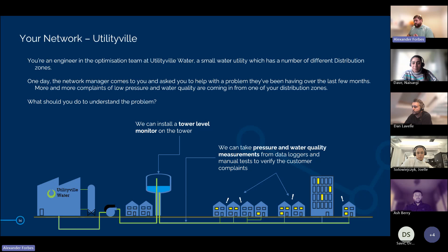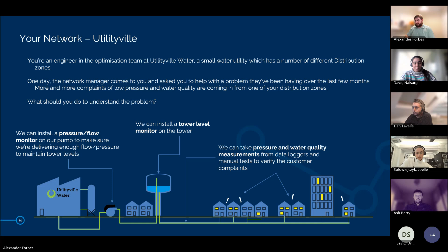Maybe what we do, we know that this area is probably fed by this water tower, so we can install a water tower level monitor on the tower, make sure that we're not getting low water level in the tower. And then we can install some pressure and flow monitoring on our pump set as well to make sure that we're actually delivering the flow required to get into the tower and to get all the way up as well.